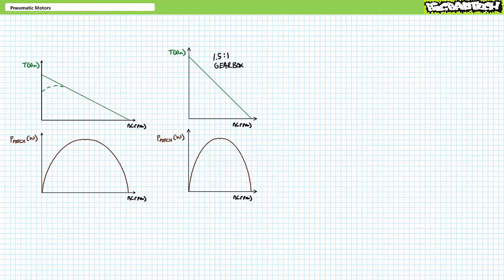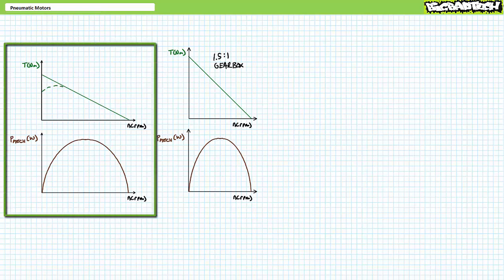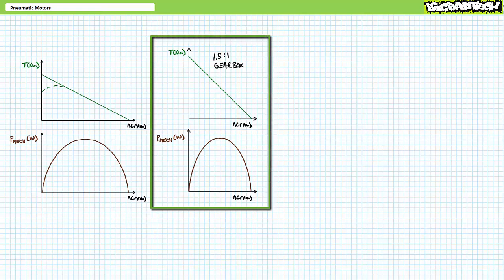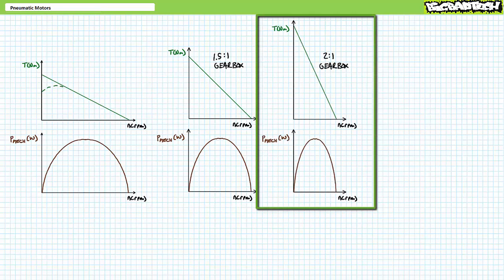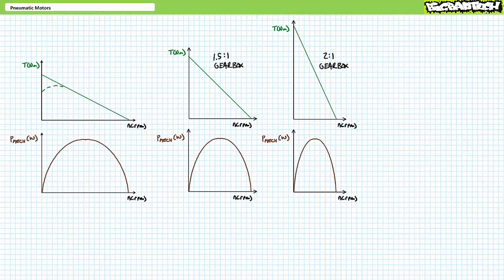Lastly, I should mention that gearboxes on the head of air motors may modify the speed torque curve. For example, an air motor lacking a gearbox may exhibit the behavior as illustrated in this chart. However, that exact same air motor employing a reducing gearbox, where speed is exchanged for torque, might exhibit the following behavior. Similarly, the exact same motor fitted with an entirely different gearbox, with an even greater reduction ratio, might exhibit plots that look like this. Note that the height of the power curve, the product of increased torque, yet equally reduced speed, does not change in height, but only width. Depending upon application, a gearbox may not be fitted to an air motor.